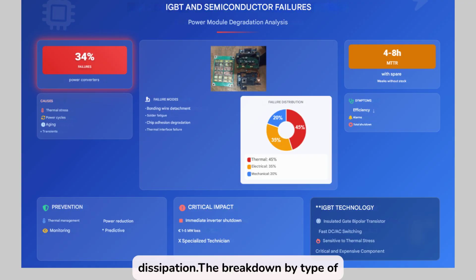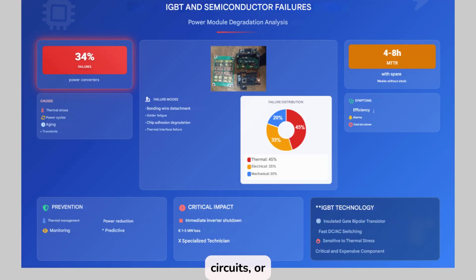The breakdown by type of failure can be thermal, 45%. The main cause of failure and difficult to detect without specific sensors. Electrical, 35%. Associated with overloads, internal short circuits, or transients. Mechanical, 20%. Related to vibrations, structural fatigue, or poor assembly. MTTR, mean time to repair, between 4 and 8 hours if spare parts are available on site. This time can extend to several days or weeks if stock is not available, seriously impacting system availability.